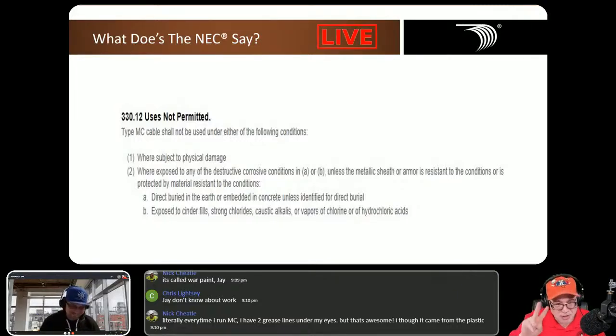So number two, it says we're exposed to any destructive, corrosive conditions in A or B, unless -- and this is important, folks, listen -- unless the metallic sheathing or armor is resistant to the conditions or is protected by material that's resistant to the conditions. Now I'm going to tell you right now, PVC jacketed MC is resistant to destructive corrosive conditions. If you look at any chemical chart that talks about PVC material, most of the applications you'll deal with include cinder fills, chlorides, alkalis, caustics, vapors, chlorine, bromine, hydrochloric acids.